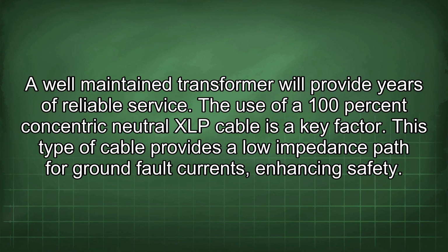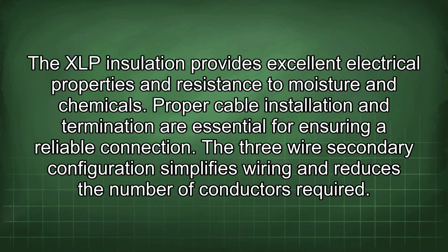The use of a 100% concentric neutral XLP cable is a key factor. This type of cable provides a low impedance path for ground fault currents, enhancing safety. The XLP insulation provides excellent electrical properties and resistance to moisture and chemicals. Proper cable installation and termination are essential for ensuring a reliable connection.